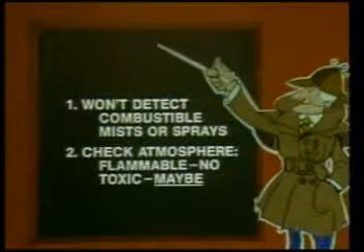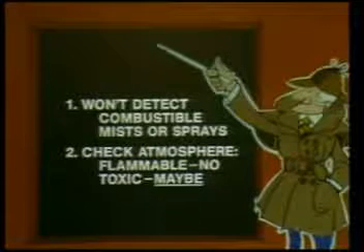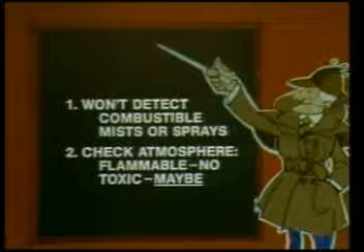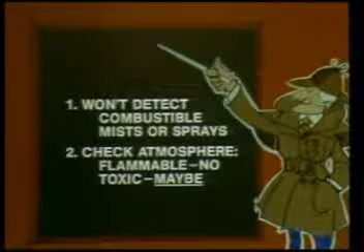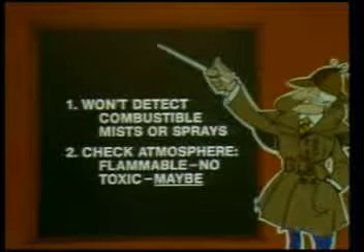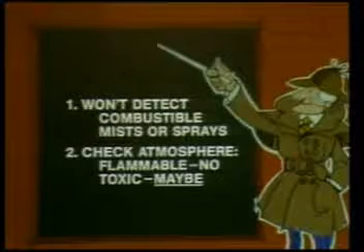Two final points. The instrument will not detect combustible mists or sprays, such as lubricating oil, or explosive dusts like grain or coal dust. And always remember that although your tests may show the atmosphere is safe from a flammability standpoint, it could still be toxic to workers in the area. Always check with your supervisor to see if this is a consideration.